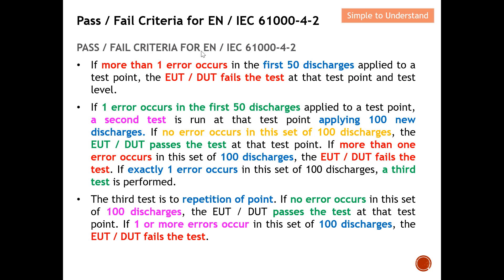If exactly one error occurs in the second set of 100 discharges, you must do a third test. In the third test, if there is no error in the first 100 discharges, you pass. However, if there is one or more errors in this 100 discharges, your EUT fails the test. This is the complete pass/fail criteria for EN/IEC 61000-4-2.